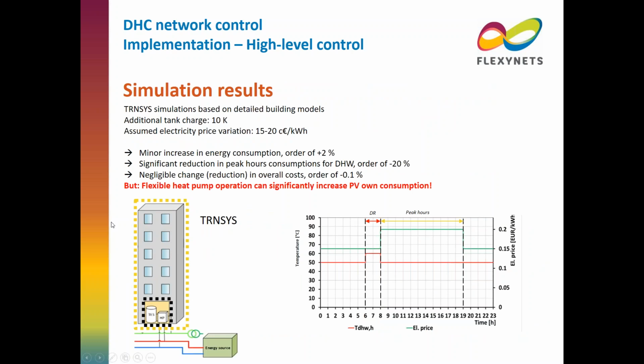There have been several examples where we did some calculations on this. What we found is that we increase the electricity consumption by only 2% in this case, because we have higher temperatures, for example, in the storages. But we can significantly reduce peak loads within the district heating network by 20%. Overall, the reduction of costs was quite low in this case.